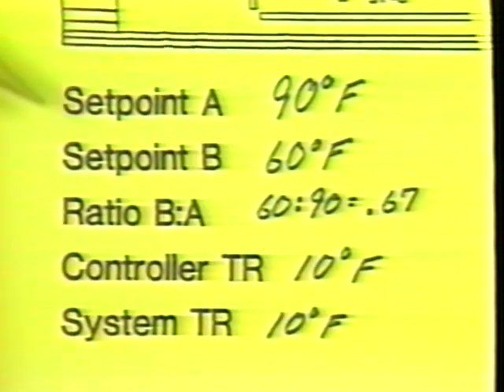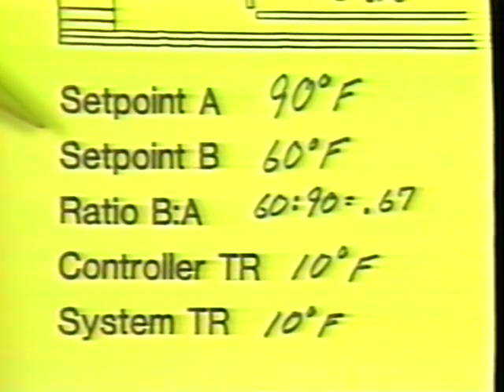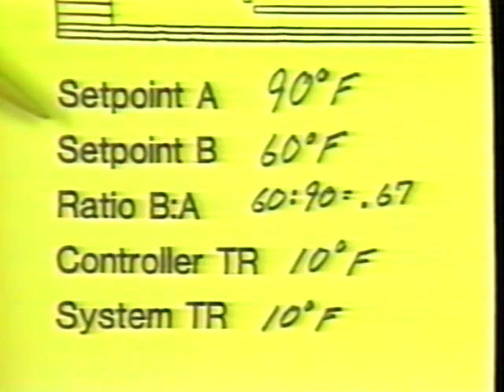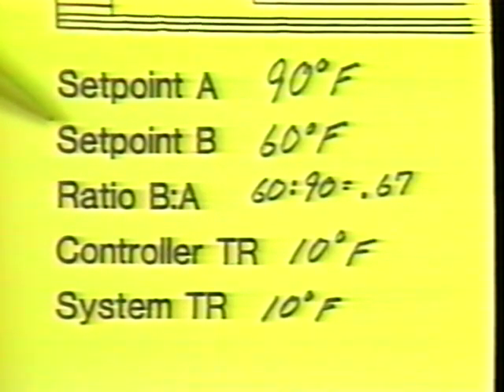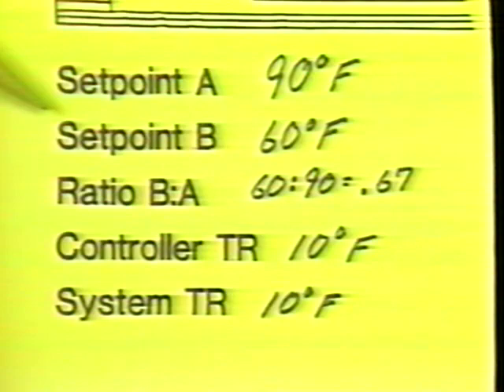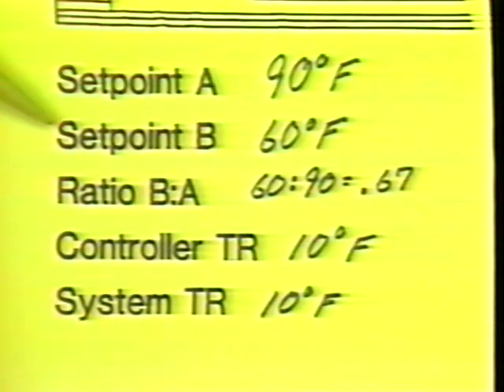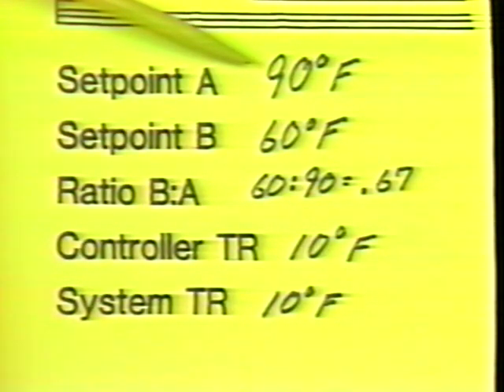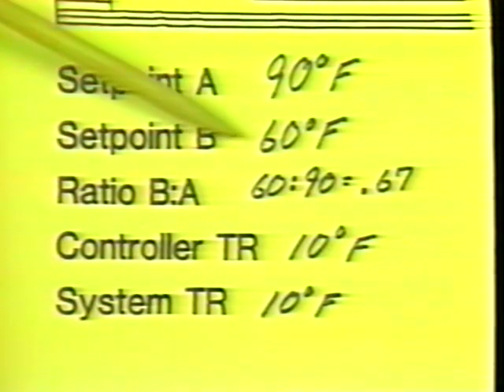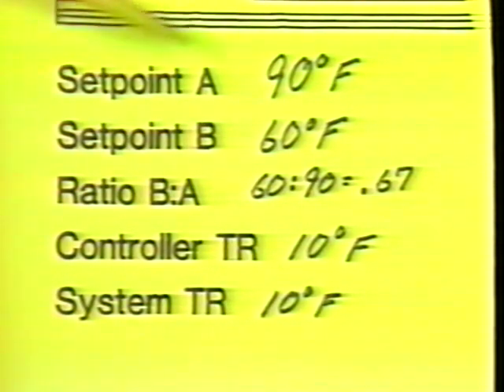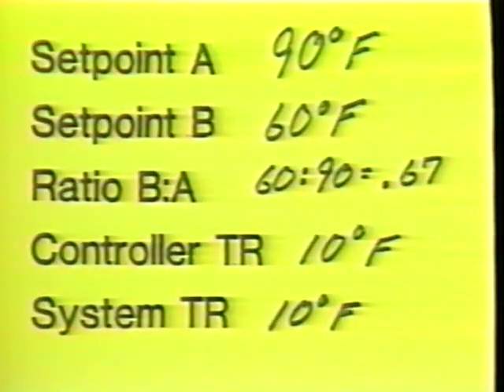Set point A and set point B are typically taken to be the lowest values on the hot water reset. However, they can be any combination of values from the reset schedule that are programmable through the two set points. In this case, we've taken the hot water temperature of 90 degrees when the outside air temperature is 60 degrees as our set points A and B. The ratio setting, as always, will be the relationship of B to A.